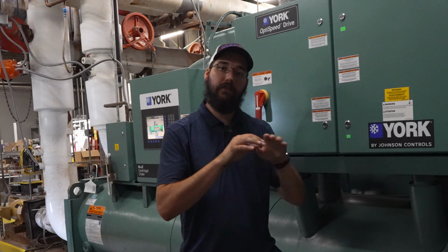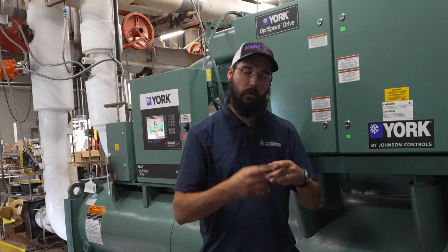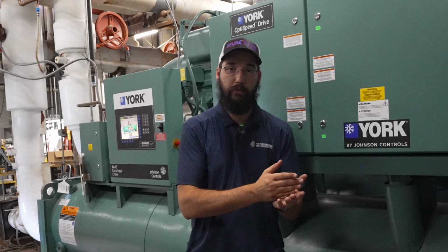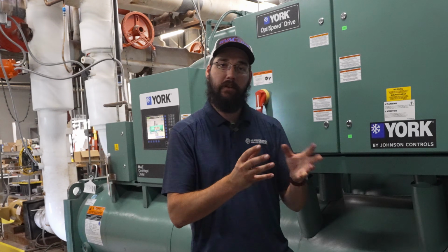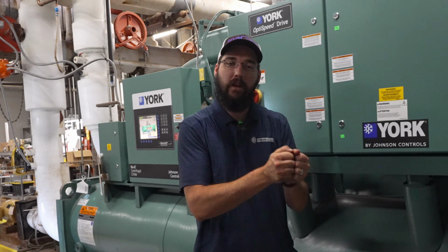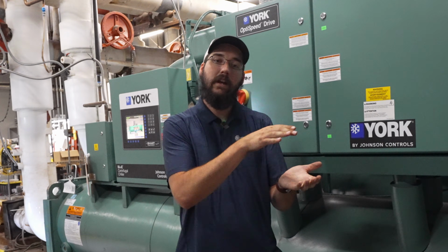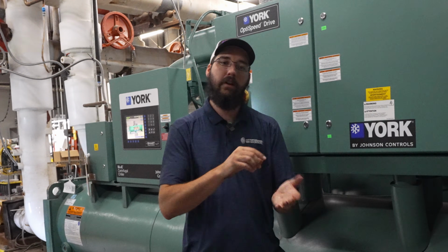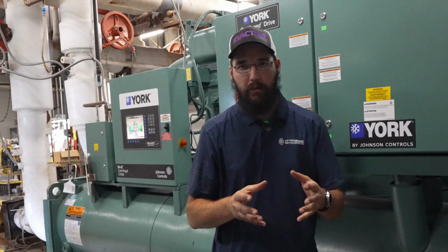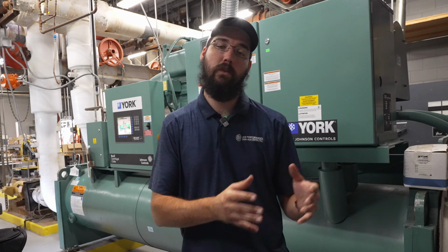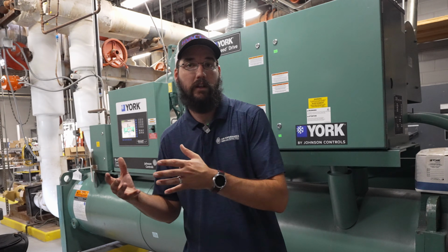What they warn you about is if that liquid level drops too low, it's going to cause turbulence on those tubes, and those tubes are going to have the ability to rub on that rack because they're not secured in any specific way. They just rest in there. So it is imperative that we don't have too much turbulence, which is going to allow a lot of movement on that tubing, which will lead to eventually rubbing a hole through it. Now, this isn't something that's going to happen overnight. This would progressively happen over a period of time and get worse and worse and worse until eventually it just leads to an all-out failure.